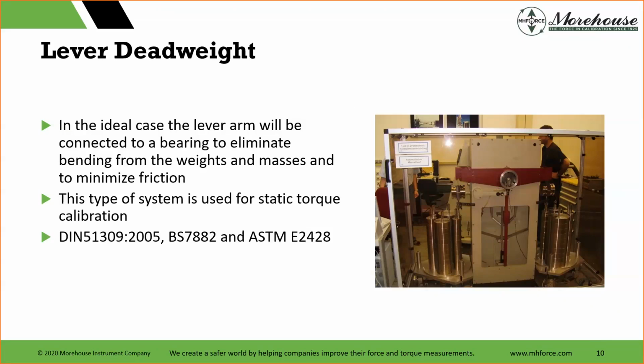This type of system is used for static torque calibration, and there are some standards, the DIN 51309, BS 7882, that's the British standard. And in this country, some people may not know about it, but it did come out in 2015. We have ASTM E2428. What's interesting about the ASTM standard, as being part of that committee, part of the E28 committee, is we did a round robin, and we did an ILC when we sent a standard to PTB. They calibrated it, and then we all calibrated our systems.